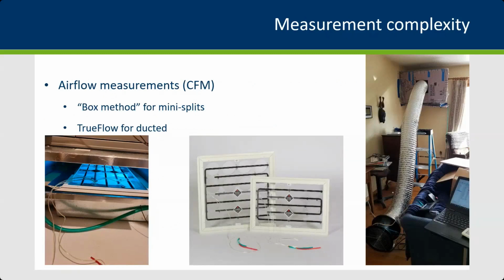One example of a field measurement that is difficult to capture on site is our airflow testing. So CE, along with other national labs, research groups, and sensor manufacturers, such as the Energy Conservatory, have conducted a lot of testing and trials to try to understand and improve the accuracy of these airflow measurements. We are happy with the measurements that we do get. We do think they're fairly accurate and they're fairly consistent with the manufacturer specifications, though we usually get a slightly lower airflow than what is specified by the manufacturers.